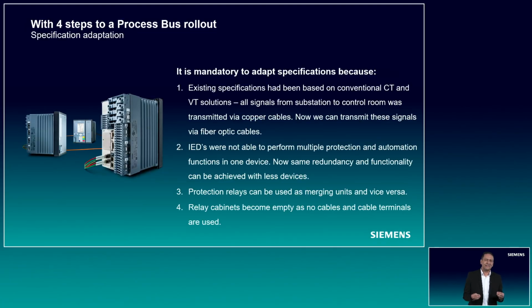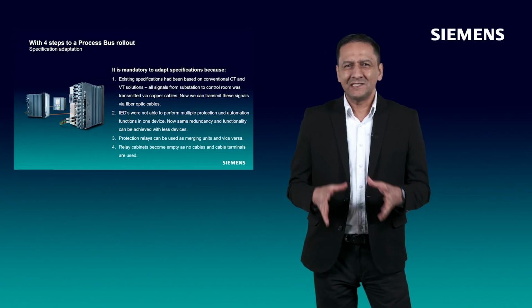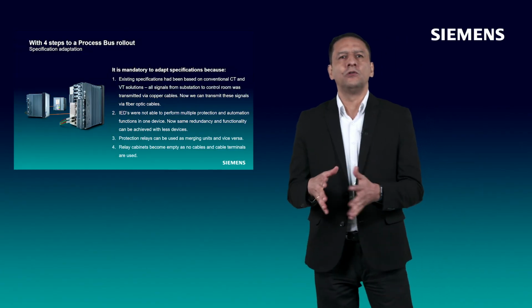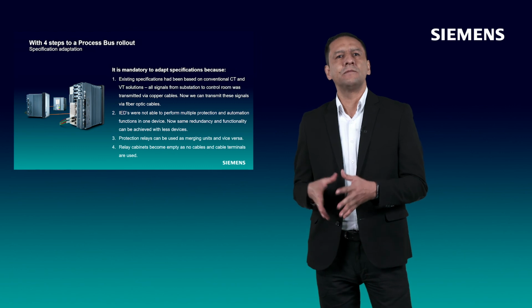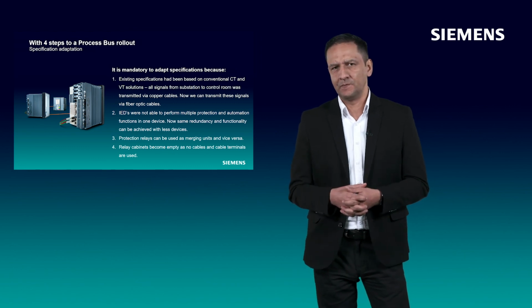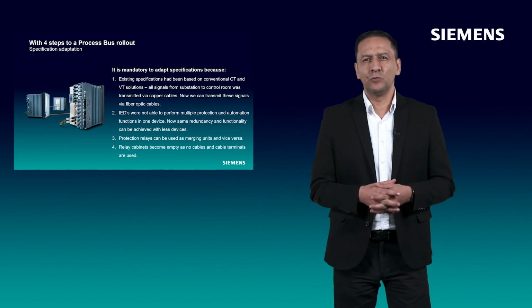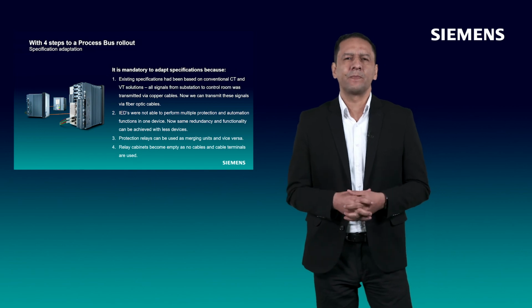Now, let's discuss why it's necessary to change existing customer specifications of conventional substations. First of all, existing specifications had been based on conventional current transformers and voltage transformer solutions. All signals from the substation to the control room were transmitted via copper cables. Copper cables had to be laid in cable trays.